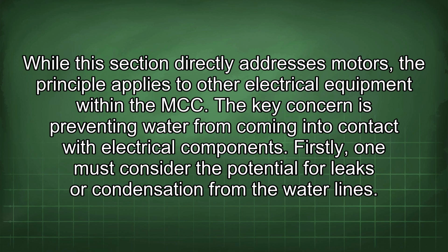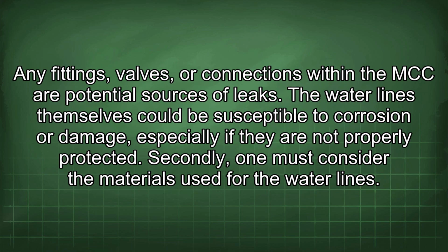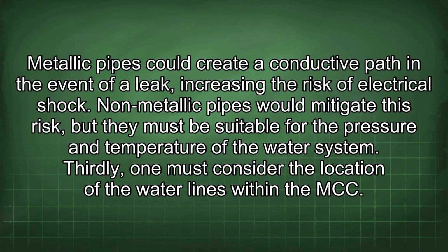Firstly, one must consider the potential for leaks or condensation from the water lines. Any fittings, valves, or connections within the MCC are potential sources of leaks. The water lines themselves could be susceptible to corrosion or damage, especially if they are not properly protected. Secondly, one must consider the materials used for the water lines. Metallic pipes could create a conductive path in the event of a leak, increasing the risk of electrical shock. Non-metallic pipes would mitigate this risk, but they must be suitable for the pressure and temperature of the water system.